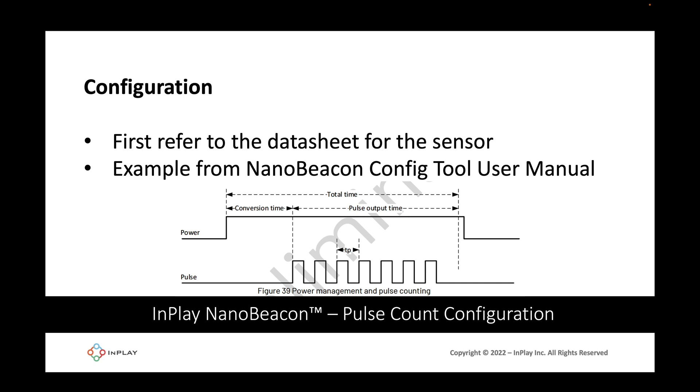The conversion and the pulse output times typically range from 30 to 60 milliseconds each. The second parameter that we need to figure out is the period of the pulse, labeled tp in the figure. This is essentially the time between two pulses, which typically ranges from a few microseconds to tens of microseconds. Finally we'll need to determine whether we want to count the rising or falling edges of the pulses. In this case we'll use the falling edge count. Once we have all these parameters figured out, we can configure the IN100 to interface with our sensor.